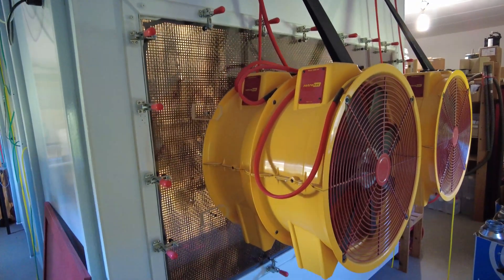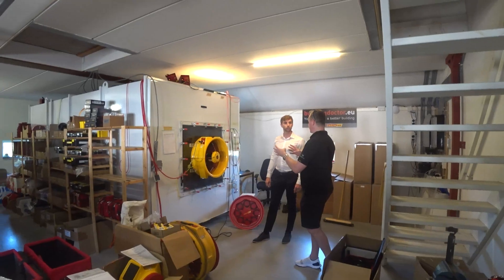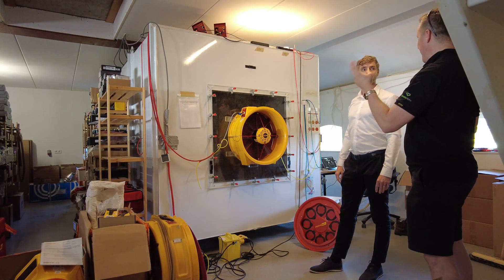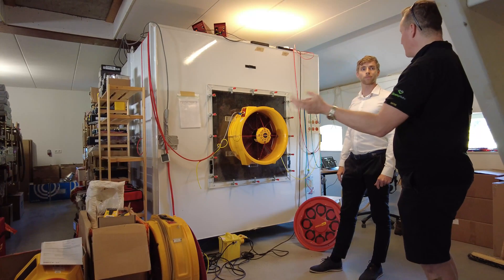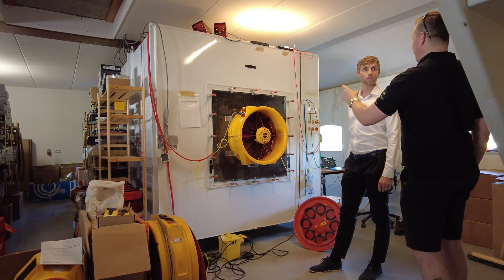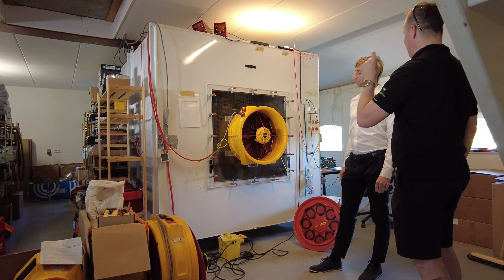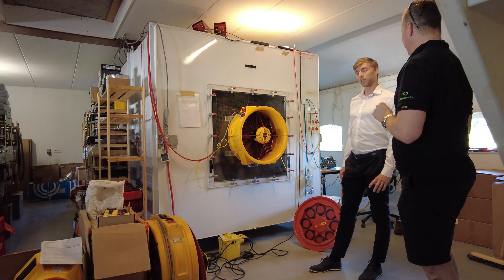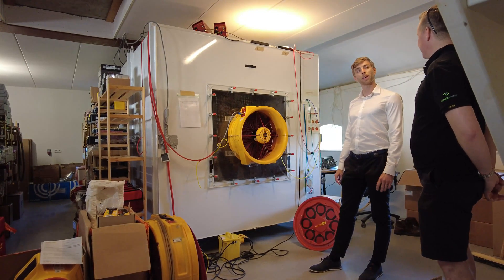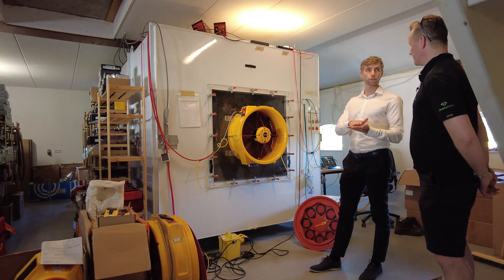One thing I see a lot, especially when someone's using a blower door but maybe isn't really trained to use it, is they just put random plugs open as long as the number adds up to what the manometer is telling you. How far out can the result be if the plugs are not left open in the correct locations as documented on the manometer? That's a good question — it does make some difference. It's recommended to make sure that whatever plugs you open matches with whatever is on your gauge or in your software.